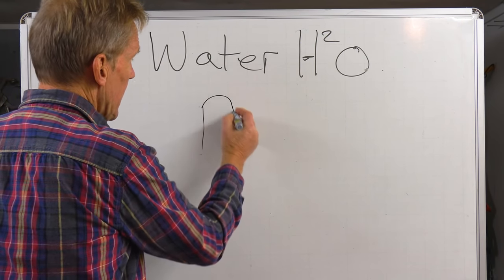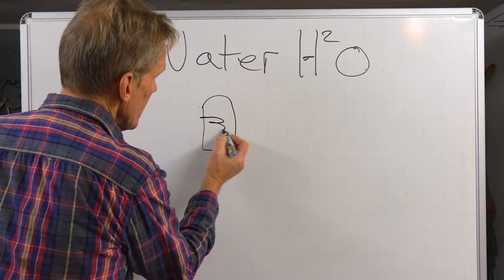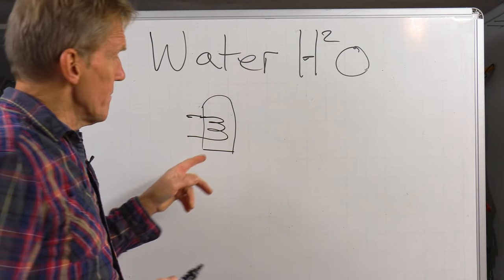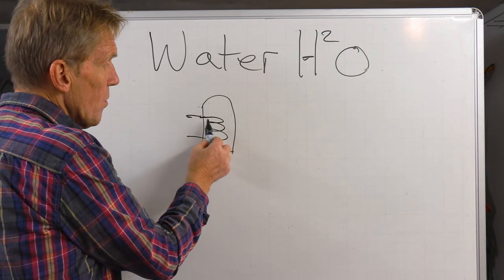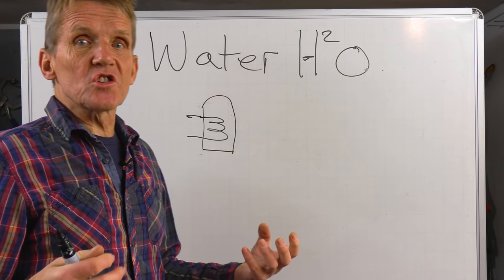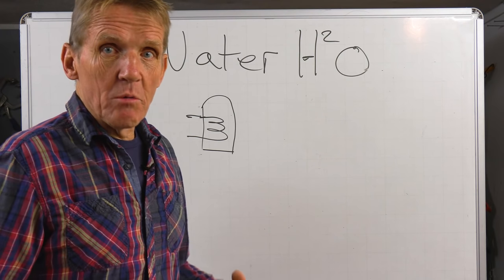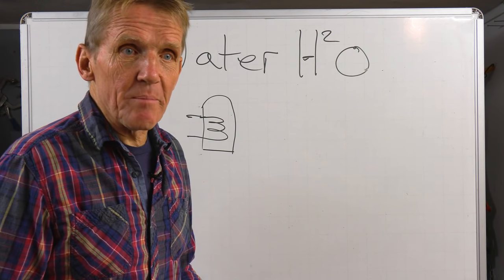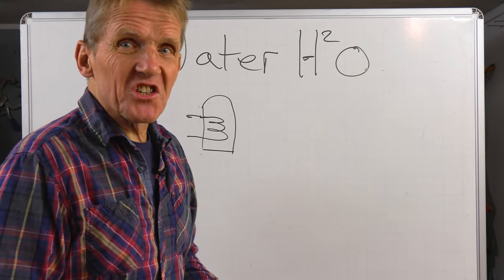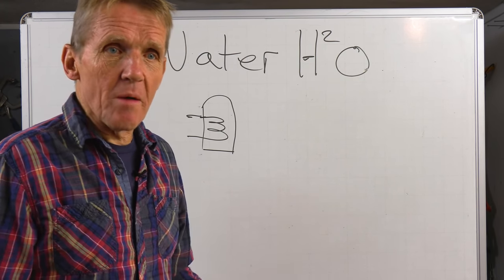So going back to our familiar cylinder with our coil running through it, if this is in a hard water area, that coil will gather scale because as you heat water up, it deposits scale. The more you heat it up, the more it deposits scale, which is why those water boilers that people have, those taps, are such a disaster in hard water areas because they're just picking up scale, scale, scale all the time.